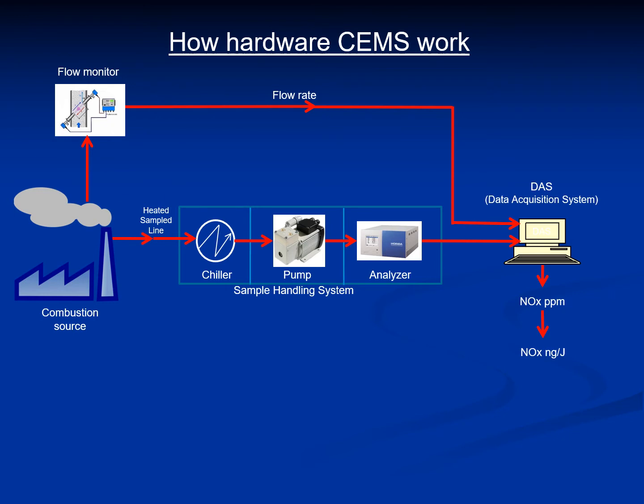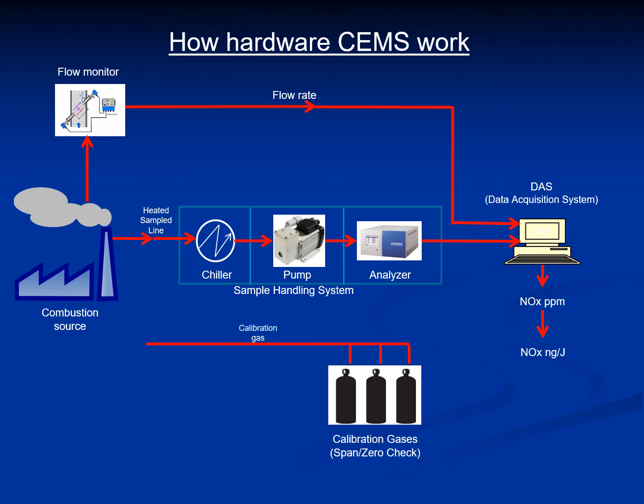To make sure that the entire CEMS works accurately, it needs to be calibrated frequently for span check, zero check, etc. To do this, calibration gases are required, which are hooked up to the sample handling system to calibrate and confirm the accuracy of the entire sampling system regularly. The entire sample handling system also needs to be housed in an enclosure to be safe from ambient conditions, and the enclosure needs to be air conditioned to maintain a controlled temperature. All of this hardware makes the installation, operation, and maintenance of the CEMS difficult and expensive.